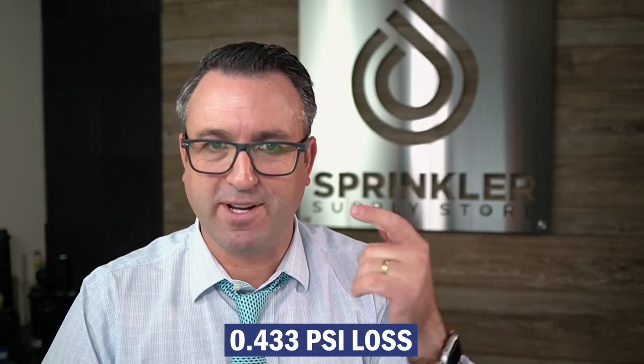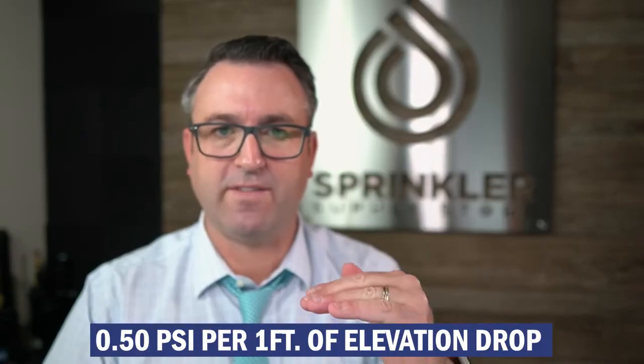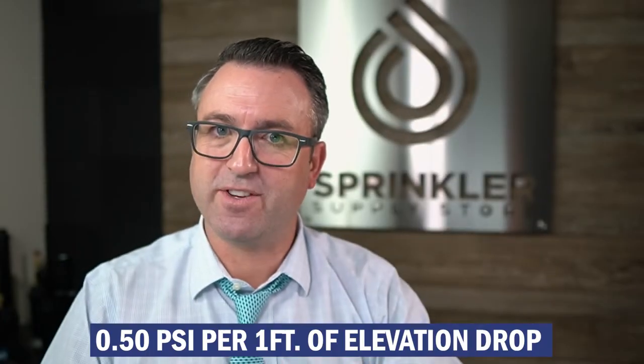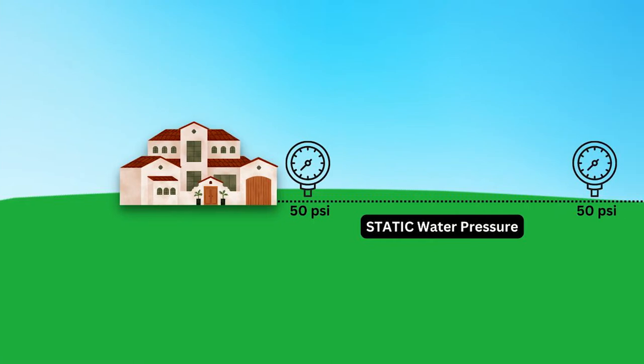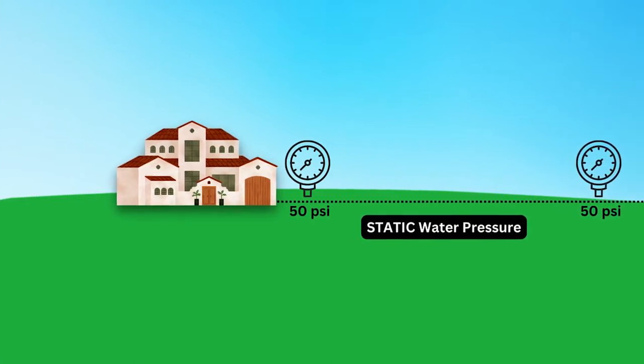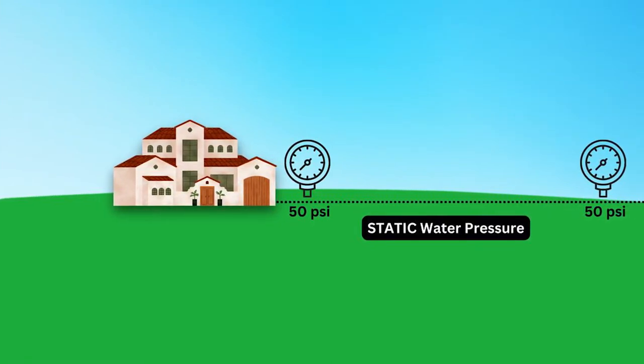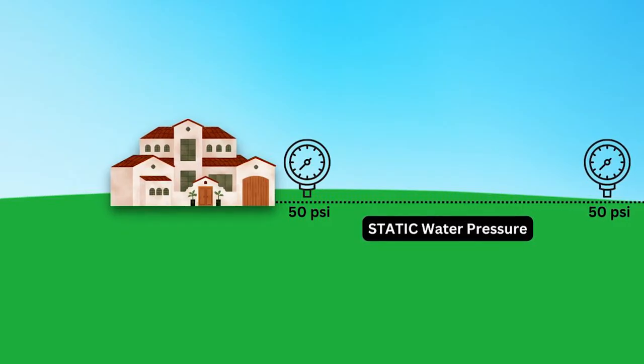Gravity accounts for losing or gaining about a half a pound of pressure per foot of elevation — it's actually 0.433 PSI per foot, but easy to remember as one half PSI for every foot of elevation. So if you're going down, you are gaining pressure, and if you go up, you are losing pressure. Static water pressure is the same at all points on the irrigation system.